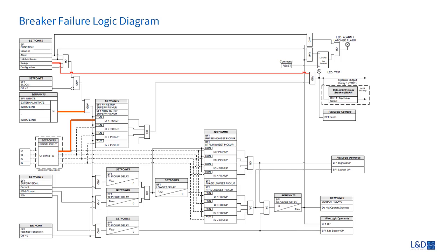The three timers correspond to three supervision conditions. T1 is used for current supervision conditions only. T2 is for both auxiliary contact and current supervision conditions. T3 is only used for breaker contact supervision. The low set delay is used for PIR pre-insertion resistor applications and should be the breaker opening time. All these conditions drive the final breaker fail operand, which is used to trip the upstream remote breaker.